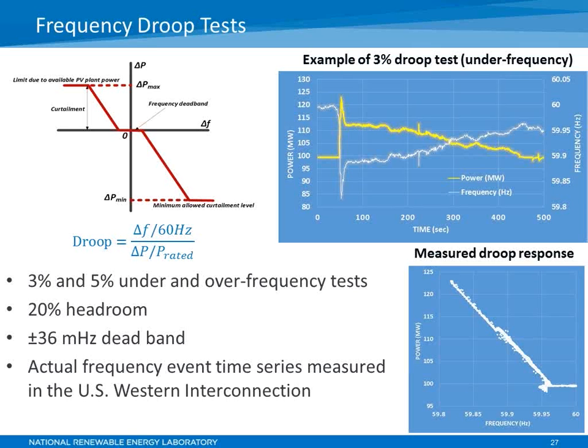Western interconnection frequency time series to a plant controller, and we measured the plant's response, providing the plant's ability to provide the frequency droop under different set points. In particular, we tested 3 and 5% under and over frequency events. The plant was commanded to have about 20% headroom. We also implemented the droop deadband. We used a conventional 36 millihertz deadband there, using the actual frequency event.